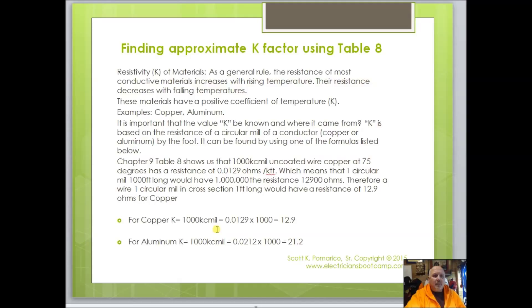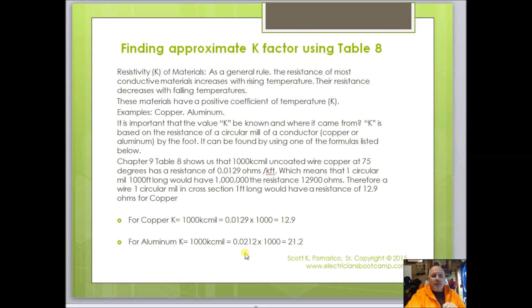Looking at Table 8: for 1000 kcmil, find the uncoated column. You'll see the number 0.0129 — multiply that by 1000 and you get 12.9. For the same 1000 kcmil in aluminum, the value is 0.0212 — multiply by 1000 to get 21.2. That's how they derive the K value.